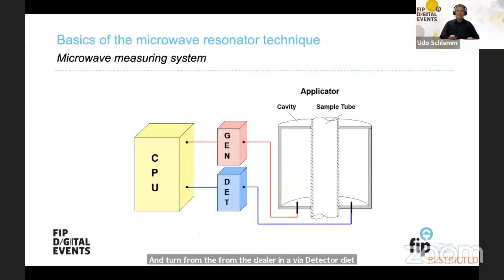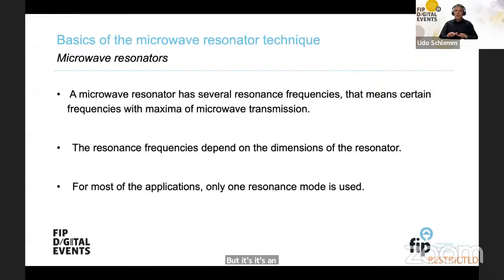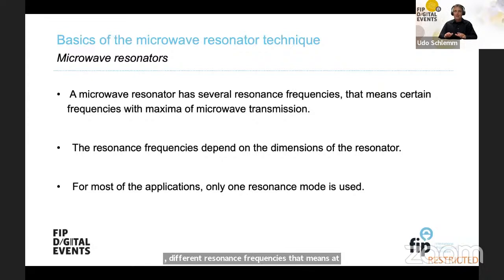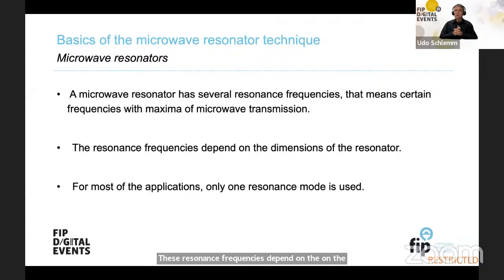In microwave measuring systems, a microwave is generated in a certain range of frequency and coupled into the applicator — the resonator — by a small antenna. By a second small antenna, the transmission of the microwaves through the resonator is measured and turned by the detector diode into voltage. A microwave resonator can look different ways, but it is an object with several resonance modes and different resonance frequencies — at certain frequencies there is a maximum of microwave transmission, and at these resonance modes a standing wave can exist inside the structure. These resonance frequencies depend on the physical dimensions of the resonator, and for most applications only one resonance mode is used.